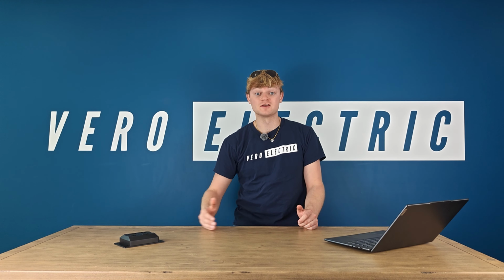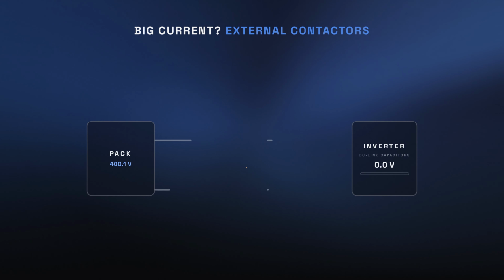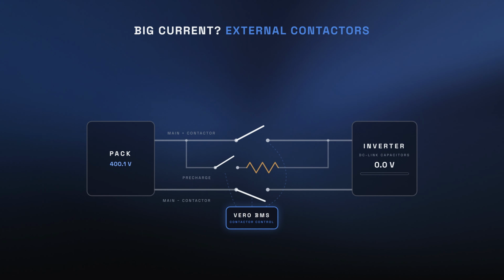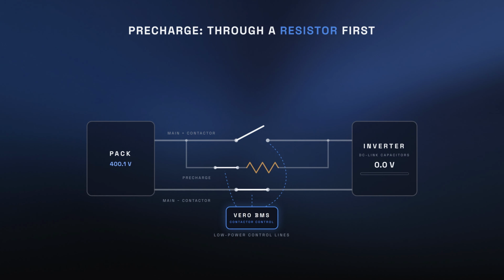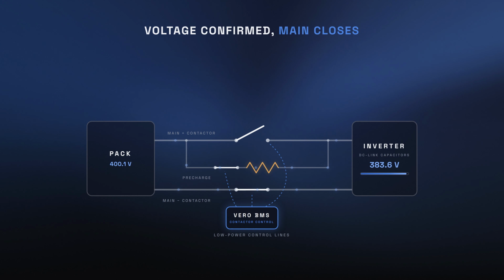Once the BMS decides what the battery can safely do, it has to go and then control the system. In a high-power battery pack, the BMS usually operates external contactors rather than carrying the full battery current through its own circuit board. If the setup calls for it, the BMS may operate a precharge sequence before closing the main positive contactor. Precharge uses a second contactor with an inline resistor to slowly charge the capacitors inside a downstream inverter or charger, limiting the initial inrush current, which can damage or weld contactors. The BMS checks that the downstream voltage rises as expected before completing the connection.